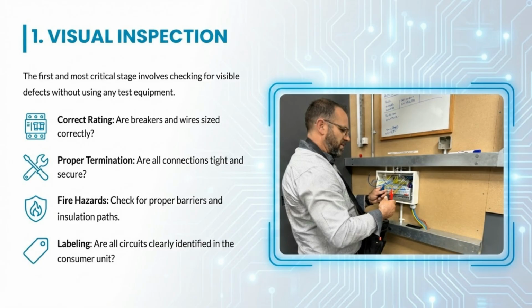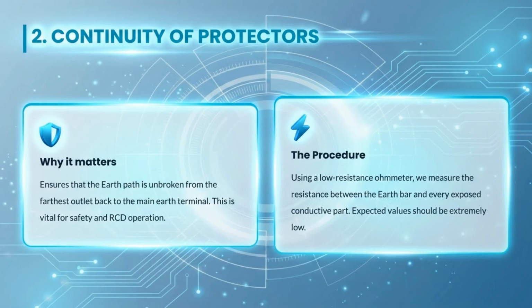industrial use. The first and most critical stage is visual inspection, checking for visible defects without test equipment. We verify correct ratings, proper termination, fire hazards, and circuit labeling. Next is the continuity of protectors. This ensures the earth path is unbroken from the farthest outlet back to the main terminal, which is vital for safety and RCD operation. We use a low-resistance ohmmeter, seeking extremely low values.